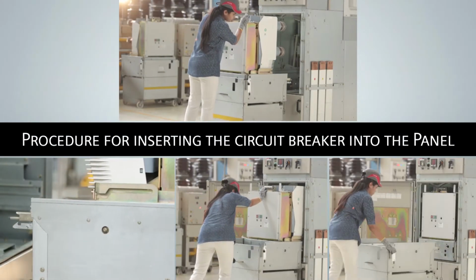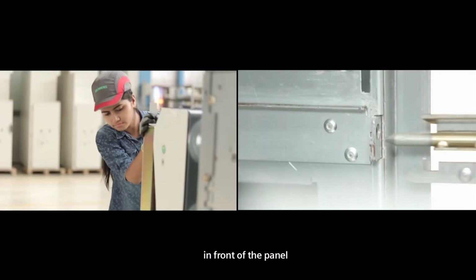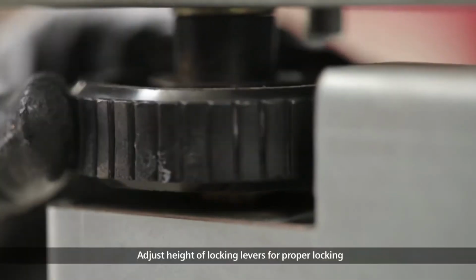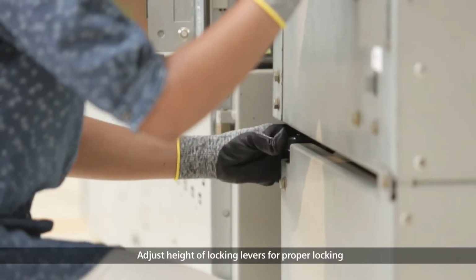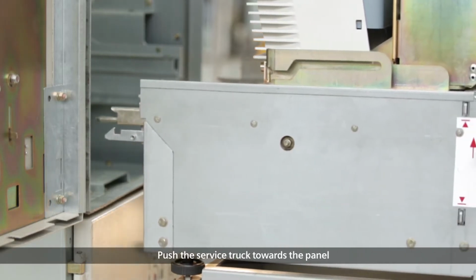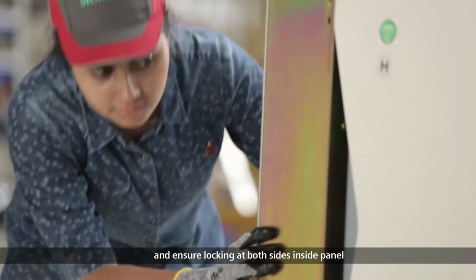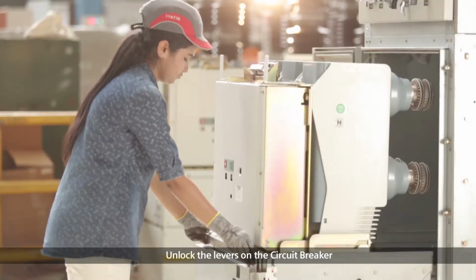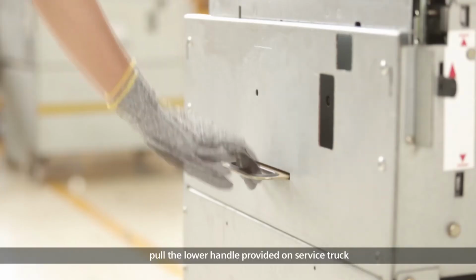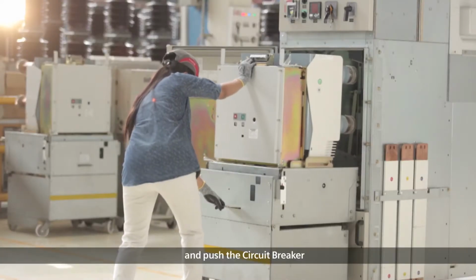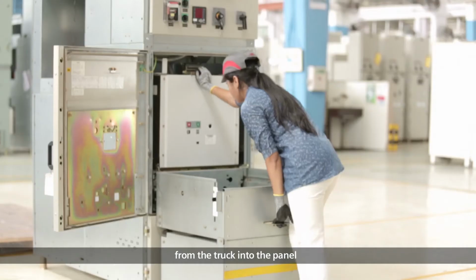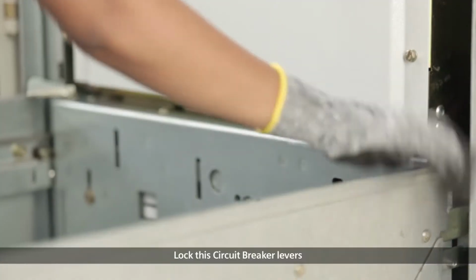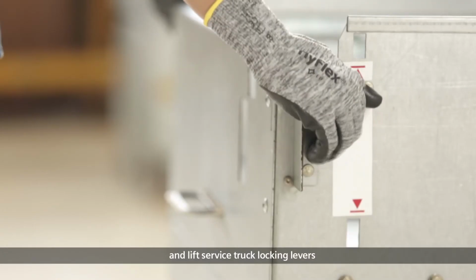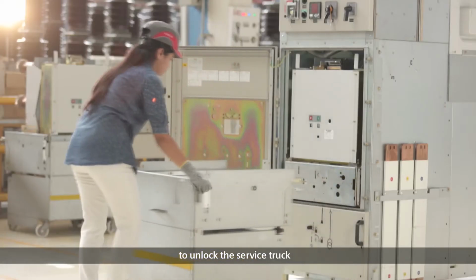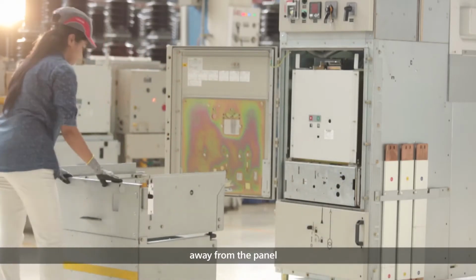Procedure for inserting the circuit breaker into the panel. Align the circuit breaker service truck in front of the panel. Adjust height of locking levers for proper locking. Push the service truck towards the panel and ensure locking at both sides inside panel. Unlock the levers on the circuit breaker. Pull the lower handle provided on service truck and push the circuit breaker from the truck into the panel. Lock the circuit breaker levers and lift service truck locking levers to unlock the service truck. Push the service truck away from the panel.